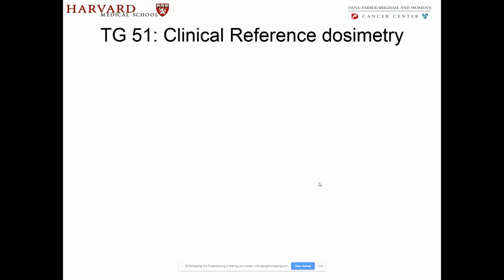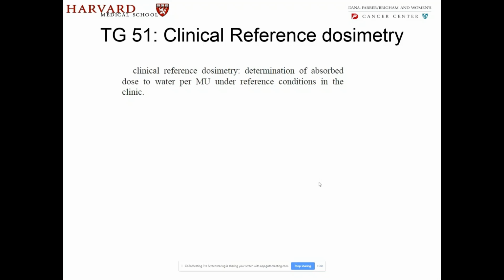So TG51, clinical reference dosimetry, one of the most important things that you need to do for calibrating your Linac. What is clinical reference dosimetry? So this is what TG51 describes as clinical reference dosimetry. It is the determination of absorbed dose to water per MU under reference conditions in the clinic.